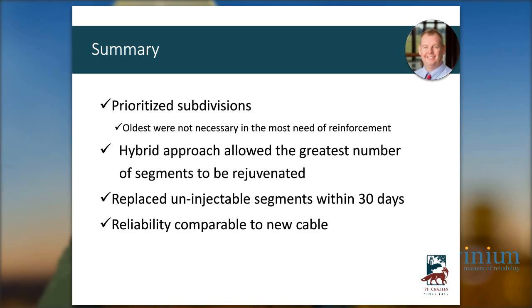Through the VLF tan delta testing, we have verified that 18 months after injection, this cable is testing a 1.0 on the TD. It's testing just like brand new crosslink poly cable, even though it's 1960s Essex cable.